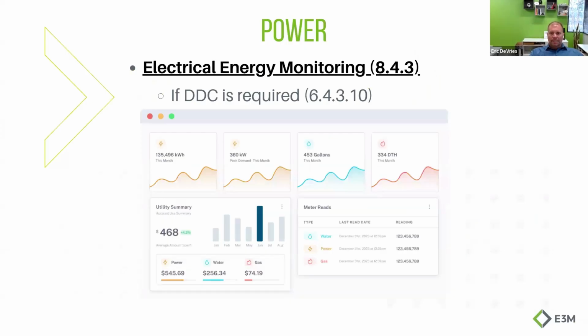If the building requires a DDC system, which is defined by the HVAC section, if in 6.4 there's a DDC system required, then you have to have a graphical interface. We're not talking a dashboard on a TV screen in the lobby, but we are talking about maybe a web interface that someone could pull up and see the real-time energy use of those different systems, broken down by system via a web interface. If a DDC system is not required, you can get away with metering all of this with just an LCD display on your power meter that you'd have to scroll through and see your different loads.